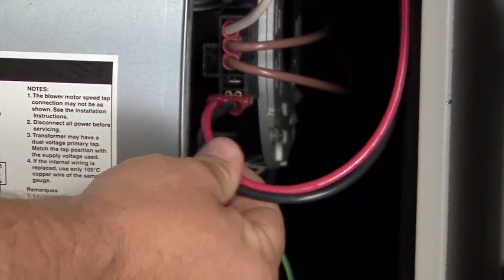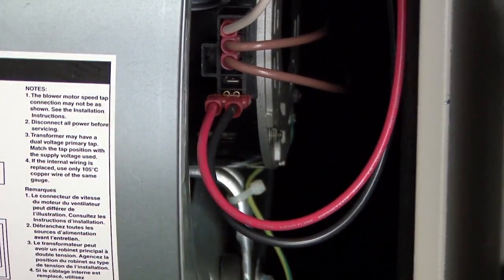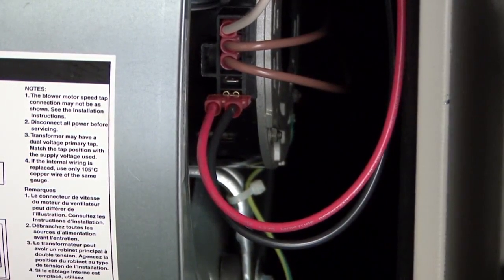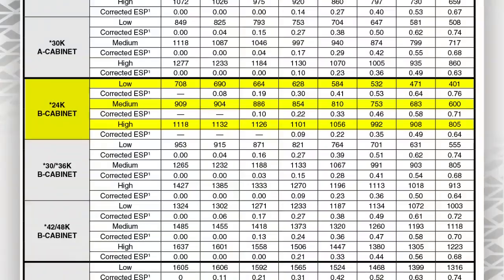On this one here right now it's going to low speed, but I can tell you installing this unit out in the field, when you've got ductwork and everything attached to it, that's going to be too low. So now you can, depending on how many kW electric heat you have in there and what tonnage unit you're working on with the heat pump, there may be times where you want to separate those. So we can give you the option of doing that. You just separate your red and black wire. So you could have red for electric heat.